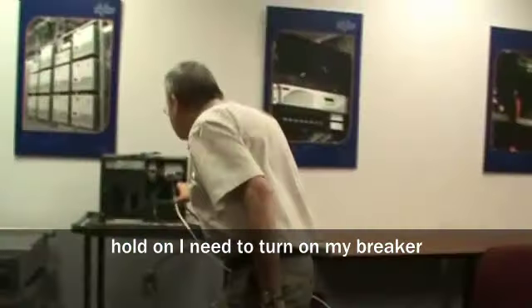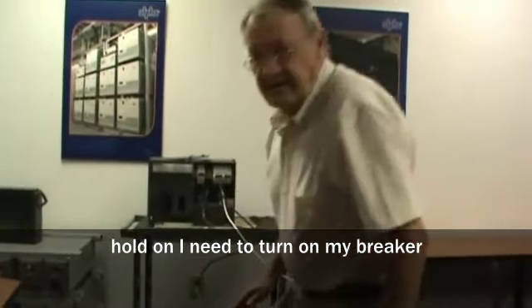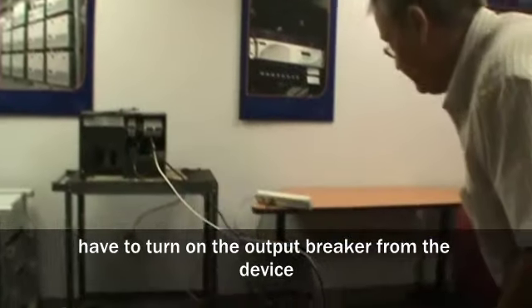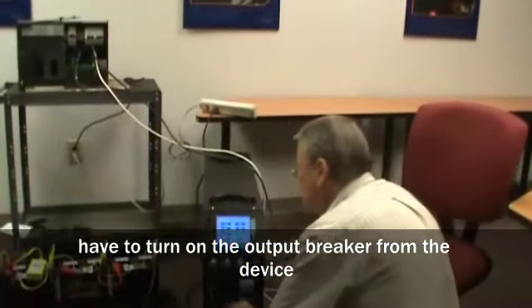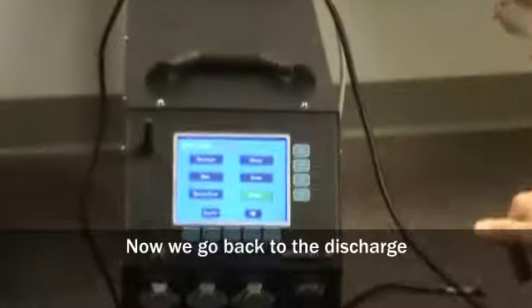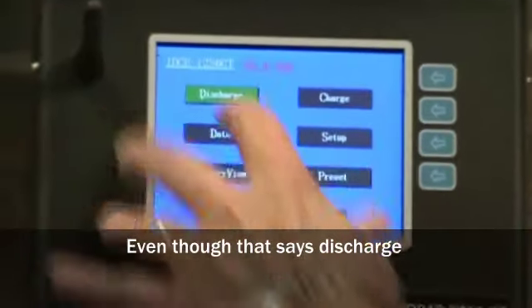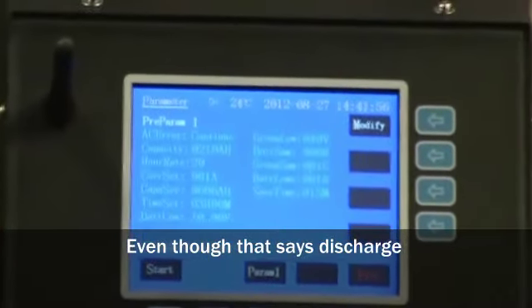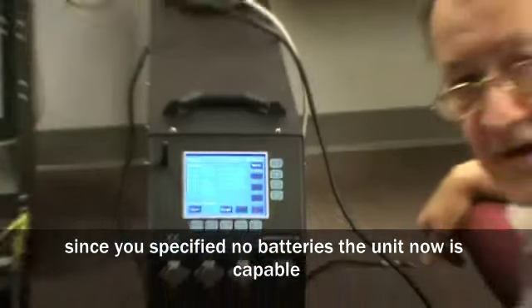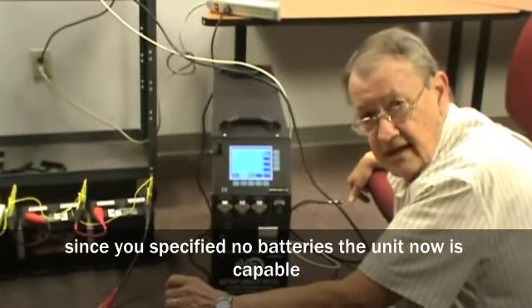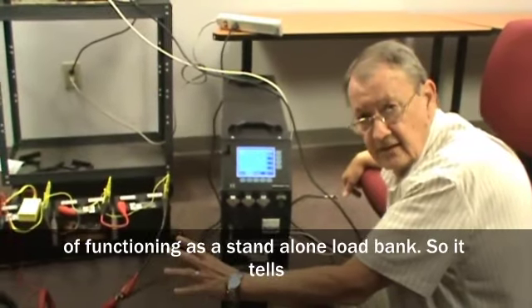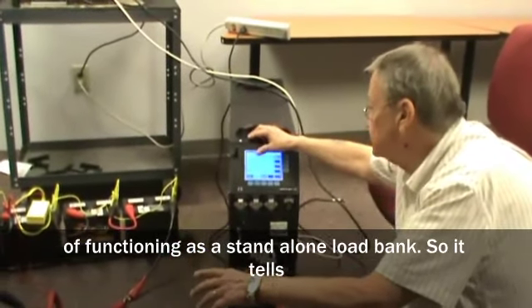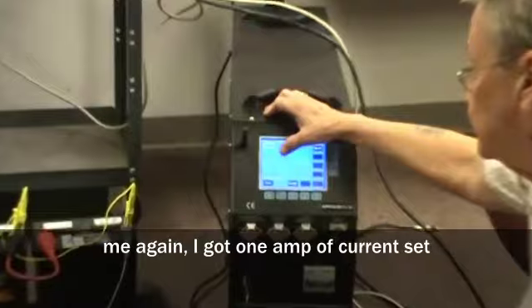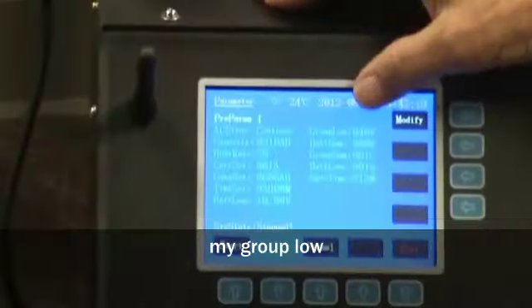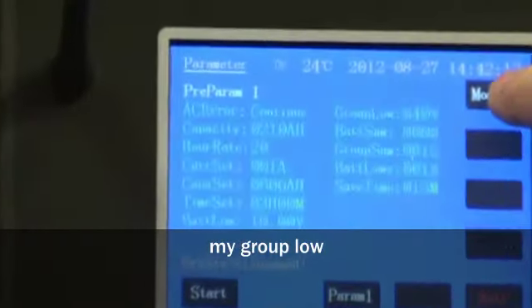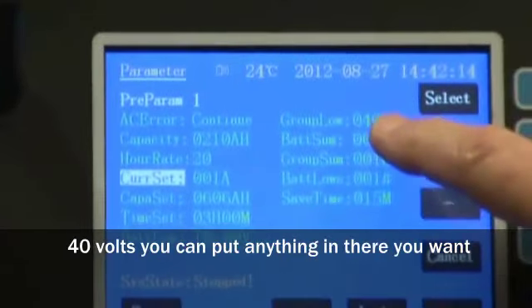Pardon me, I need to turn on the breaker. I have to turn on the output breaker from the device under test. We'll go back, now we go back to the discharge. Even though that says discharge, since you've specified no battery, the unit now is capable of functioning as a standalone load bank. So it tells me again that I've got 1 amp current set, my group load with 40 volts.